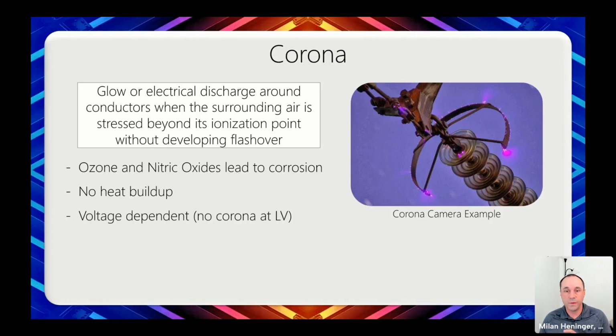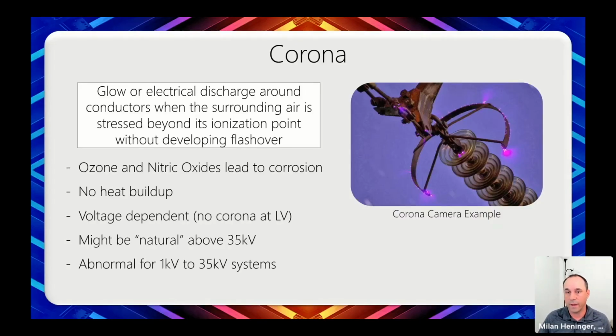So at low voltages, we do not expect to see any corona. Anything under 1,000 volts, it really doesn't occur. It may be natural above that 35 kV, which is kind of what I was talking about, is that we're going to see this effect of corona occurring above 35 kV with some regularity. It is dependent on environmental factors such as humidity and things like that. But just keep in mind that it's not necessarily harmful, especially on our high voltage stuff. But it is considered abnormal on anything between 1 kV and 35 kV.